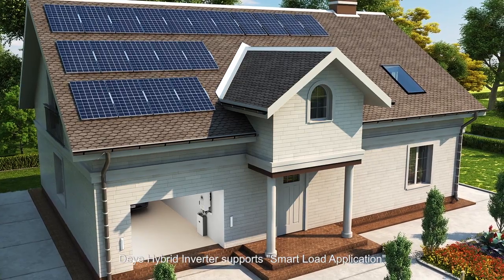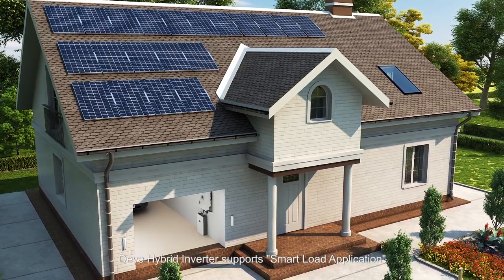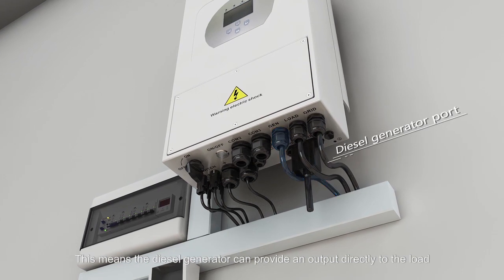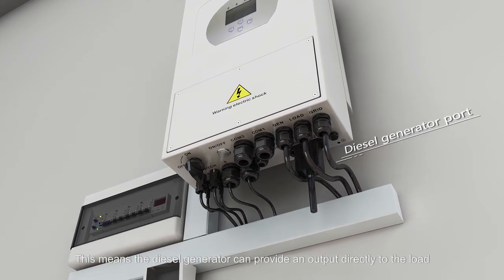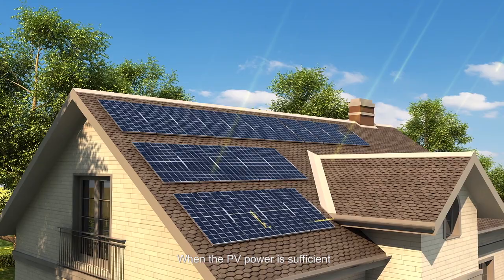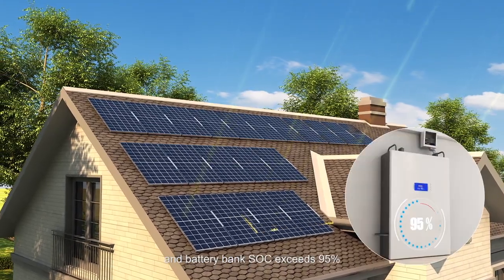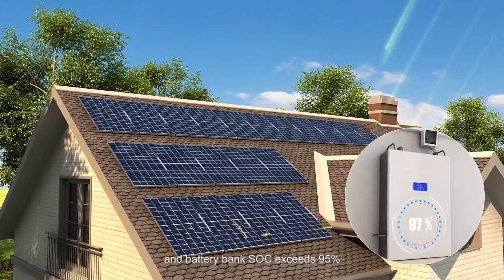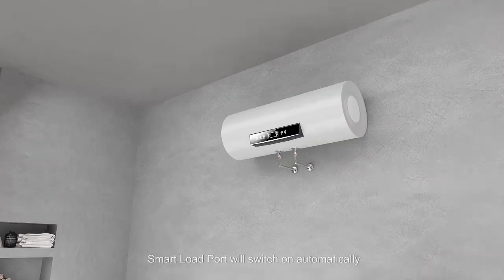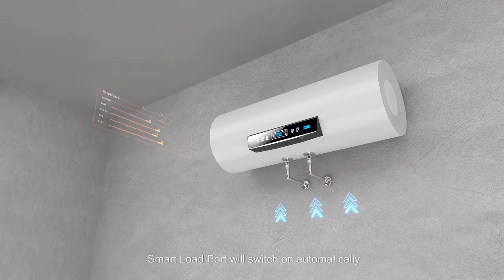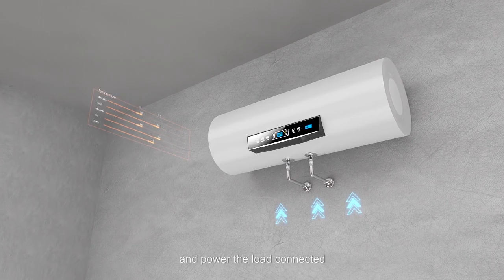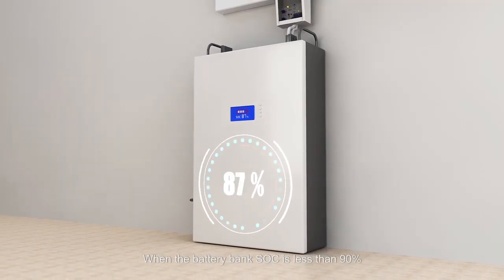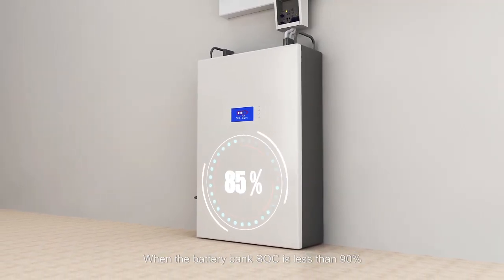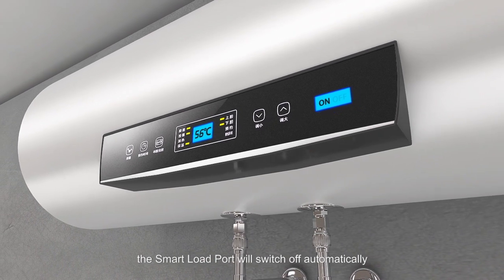Deye hybrid inverter supports smart load application. This means the diesel generator can provide an output directly to the load. When the PV power is sufficient and battery bank SOC exceeds 95%, Smart Load Port will switch on automatically and power the load connected. When the battery bank SOC is less than 90%, the Smart Load Port will switch off automatically.